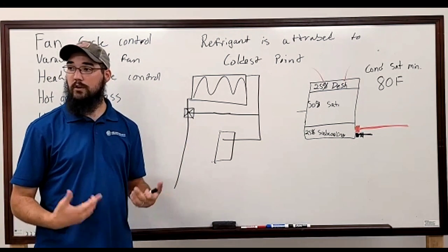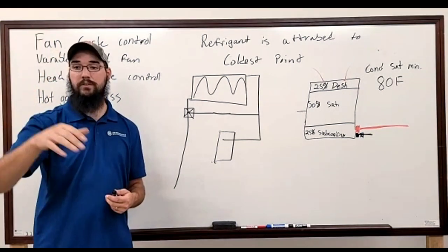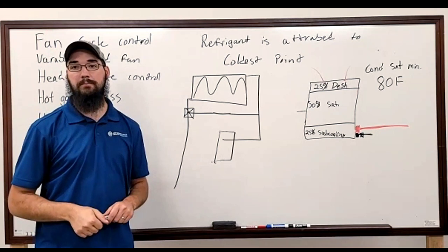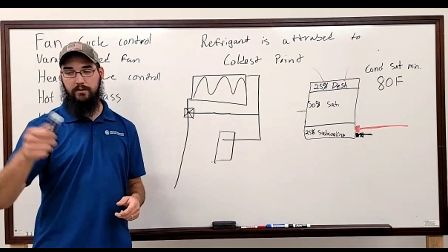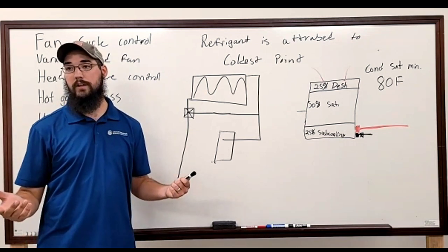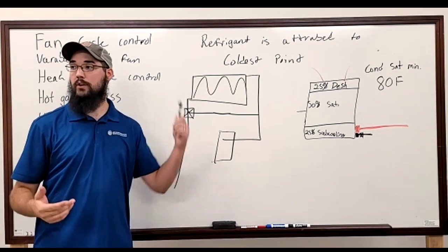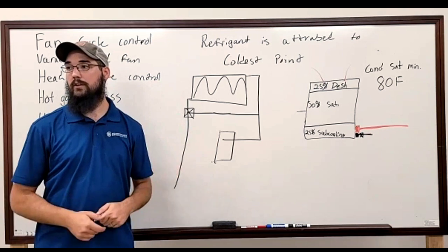Now, a process chiller or a process cooler, something of that sort, would have a different style. It doesn't look the same. So if you walked up to a walk-in cooler, it's going to have something like that on it, if it uses head pressure control at all. Some of them don't. They use fan cycle instead. It'll be one or the other.